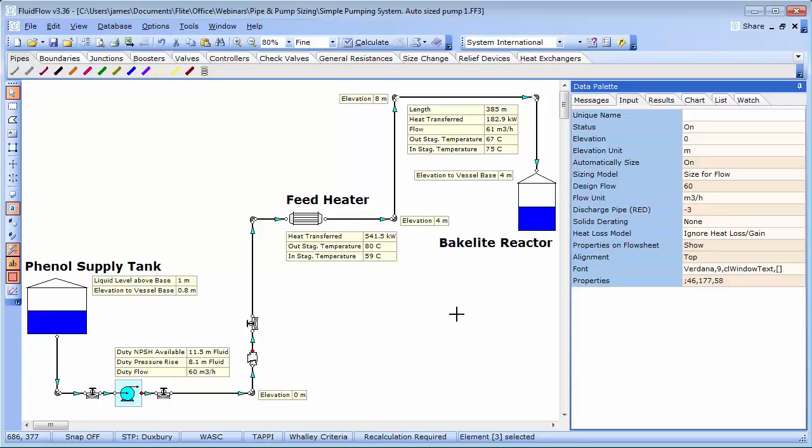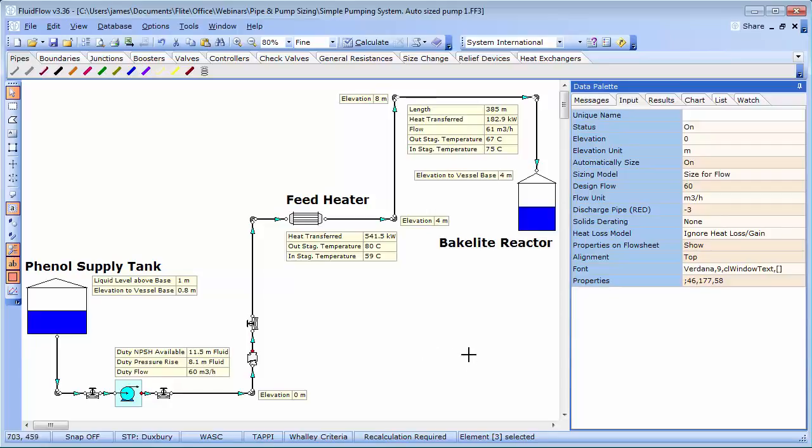And before we size the pipework, we should decide the mechanism we are going to use to deliver this 60 metre cube per hour of phenol. We basically have two options available. Use a flow control valve or other throttling device or we can use a variable speed drive on the pump. Control valve sizing is the subject of a separate webinar in the near future and as such we will choose a variable speed pump in this case.